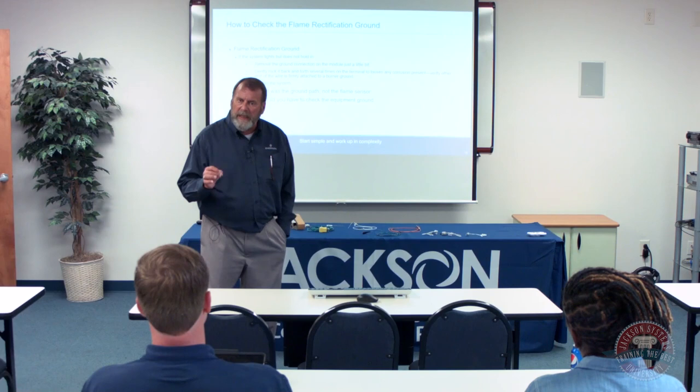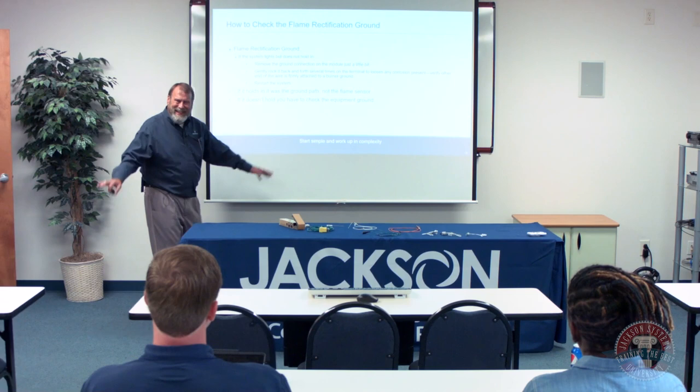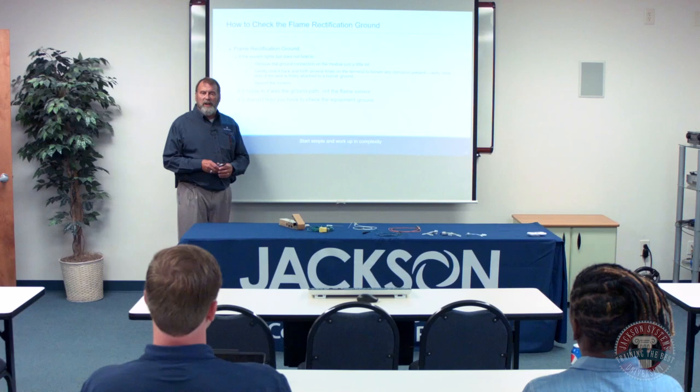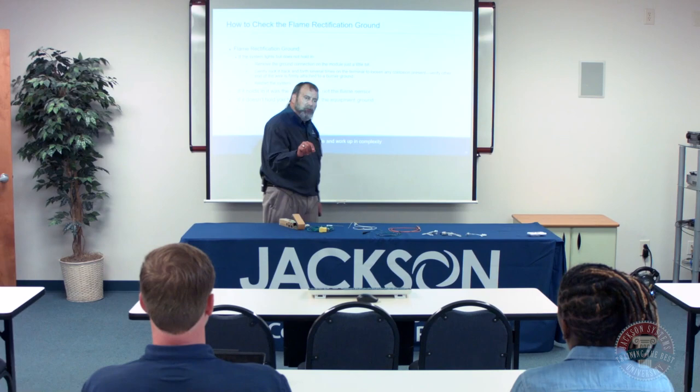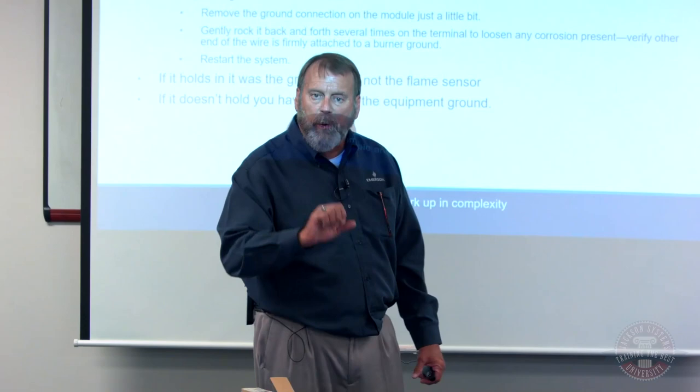So before you do anything on the cleaning, etc., if you got a flame rectification issue like Mrs. McGillicuddy, here's what I suggest you do. Before you move anything around, fire the unit off, make sure the gas valve opens, lights the gas, holds in 5 seconds or so, and shuts down. Now you've proven you got the problem. Now let's go fix it.